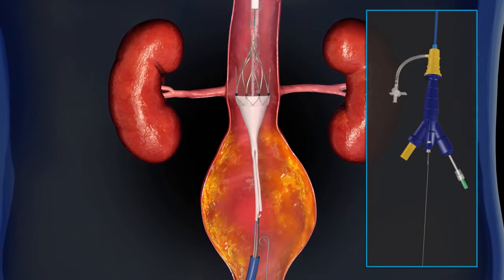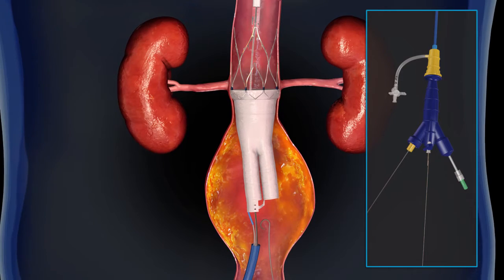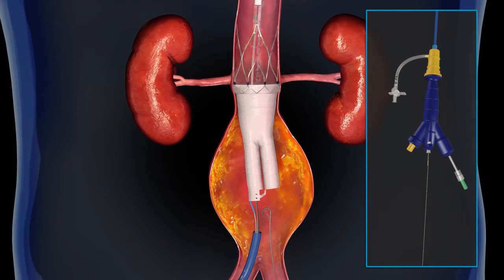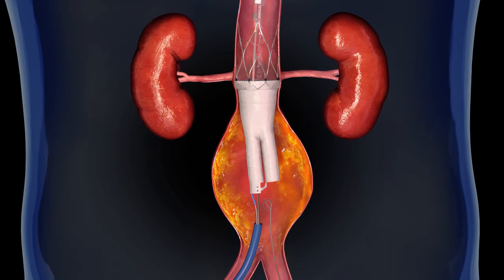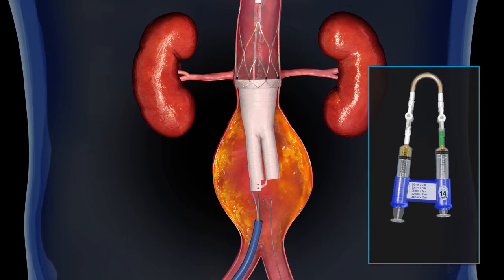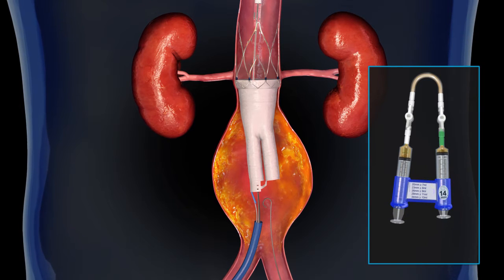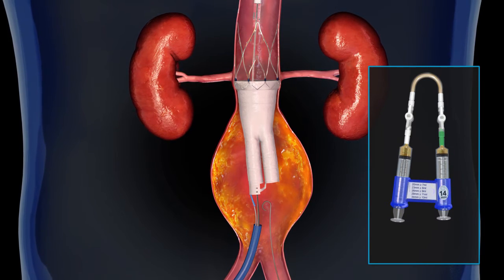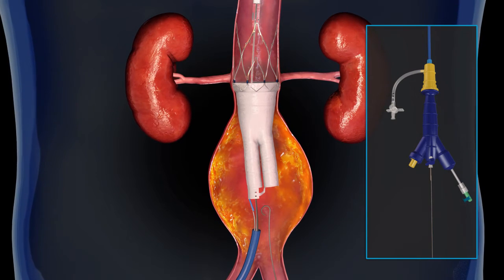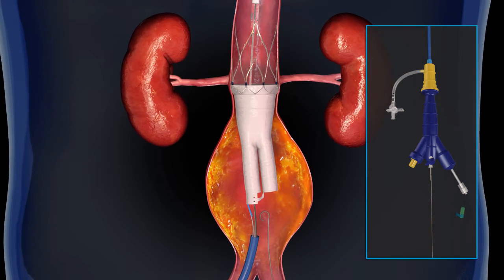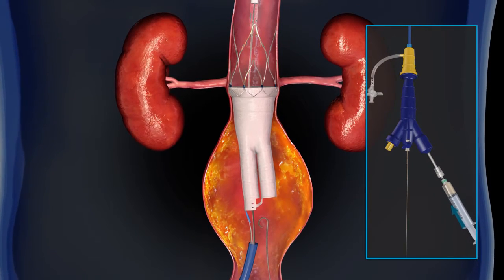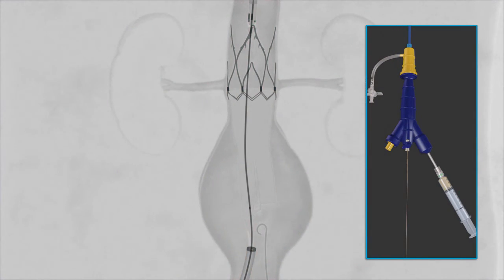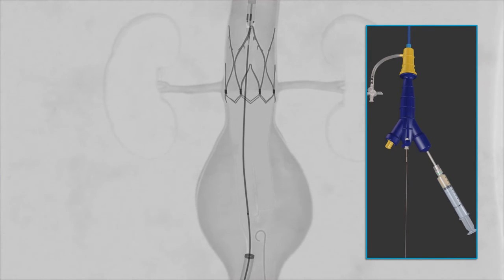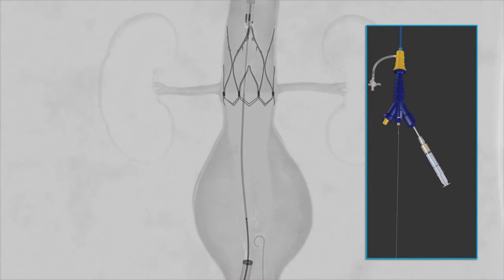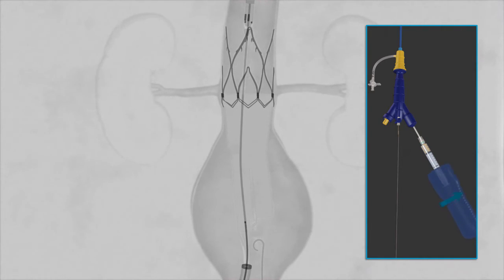The proximal stent is fully deployed by turning and pulling the second stent release knob. The stent anchors are now engaged and the graft fixed in place. The fill polymer kit stopcocks are opened and the polymer is mixed using a minimum of 20 full syringe strokes. The green cap is removed from the polymer injection port on the delivery system handle, and the polymer-filled syringe is connected. The aortic body guide wire is retracted to the RO marker distal to the aortic body. The auto-injector is pushed over the syringe plunger and locked into place by rotating 90 degrees.